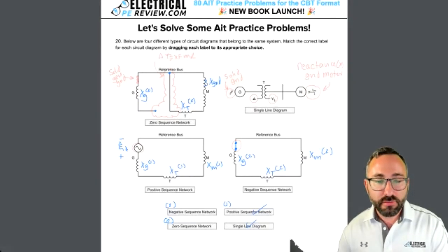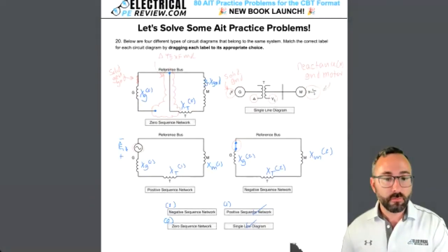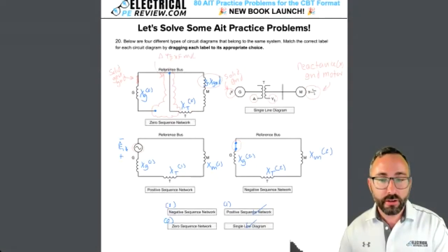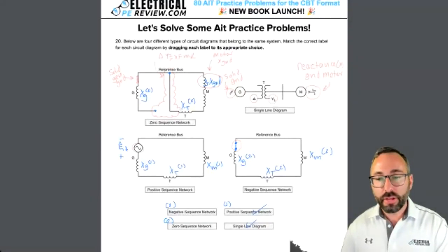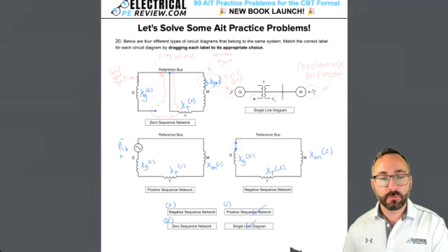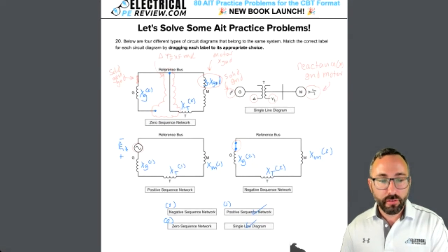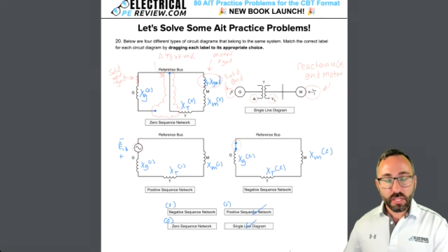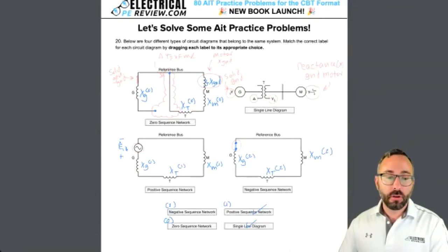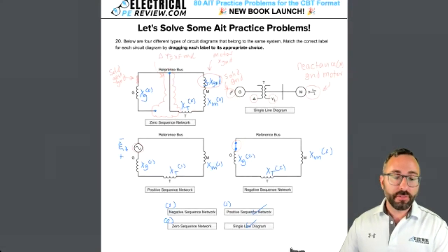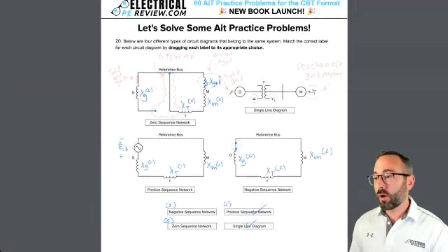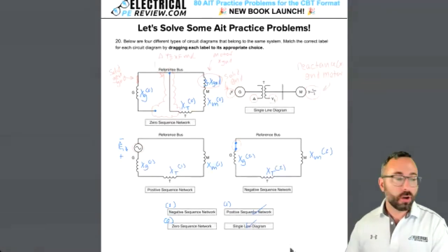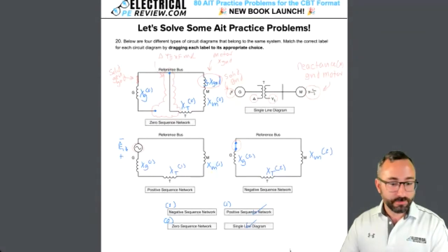Yeah, we have to multiply this value by 3. This right here, that's the motor X ground, the reactance ground for that motor. And then last, we have the motor zero sequence reactance. And that is our single line diagram, our positive sequence network on the bottom left, negative sequence network on the bottom right, and zero sequence network on the upper left.